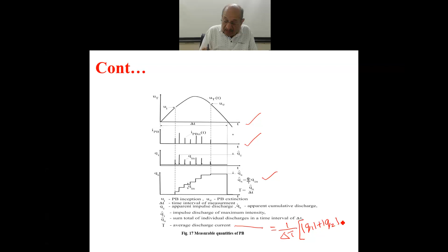The magnitude I is the average discharge current measured by the apparatus, and the average discharge current, as you can see here, is equal to 1 by delta T, then all the discharges taking place at all the locations, say Q1 magnitude plus Q2 magnitude up to Qn magnitude. So all the discharges, the magnitude of charge, that is current measured, gives rise to the average discharge current in the apparatus. That is how it is analyzed.